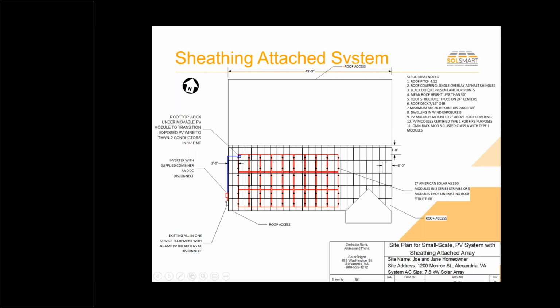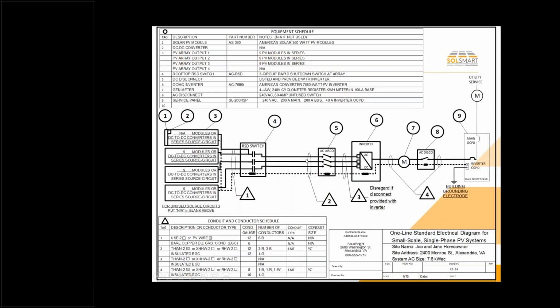We said the 4/12 pitch. Let's see. This is a truss roof, and that's what we wanted to see. So it's a manufactured truss roof. And we're using 360 watt modules. There's 27 of them, 3 series strings of 9 modules in series on the existing roof structure. And then we come off of the roof with this blue pipe, which comes down to the inverter. It's going to go straight down the side of the house, run along the edge of the house or down the eave and make it to our inverter, drop into the inverter, and then into the service entrance, which is service drop right on the corner of the house here. All right, so that's just a brief overview of what we got. Now we'll look at the electrical drawing.